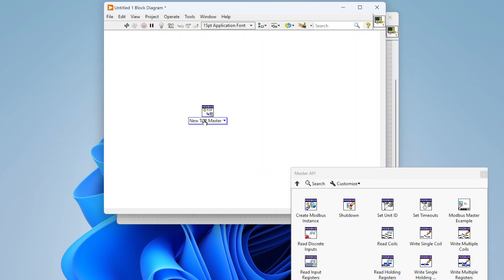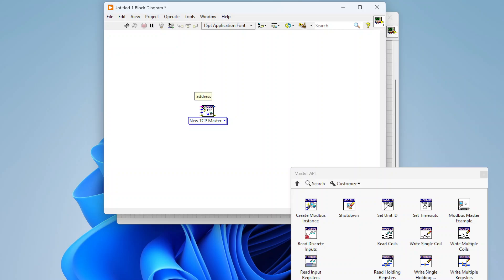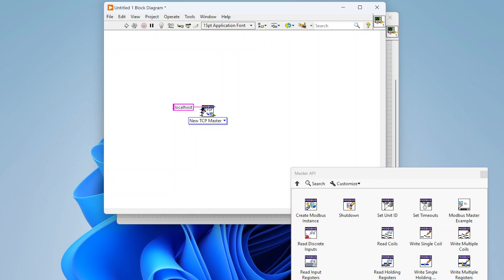For this example we'll use the master API. The Create function is polymorphic — you can select either a TCP master or a serial master depending on whether you're using Modbus TCP or Modbus RTU. Dropping the TCP master, the top-left terminal takes the address of the Modbus slave. For this demo we'll connect to localhost. The default port is 502 for Modbus TCP, which we'll leave as-is, along with the default connection timeout.